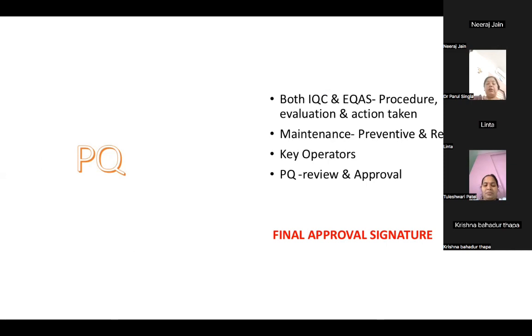You have an SOP, a standard operating procedure, to verify the performance qualification of the equipment. You can write that an IQ will be done, an OQ will be done, and then a PQ will be done. In this, you can use patient samples, your QC material, or your EQAS material. Write down a procedure. Even for a smaller equipment, you should do it. Say you are taking a small equipment and you have a small lab. You cannot do a comprehensive protocol. You can do a little bit of the things covered in operational qualification.